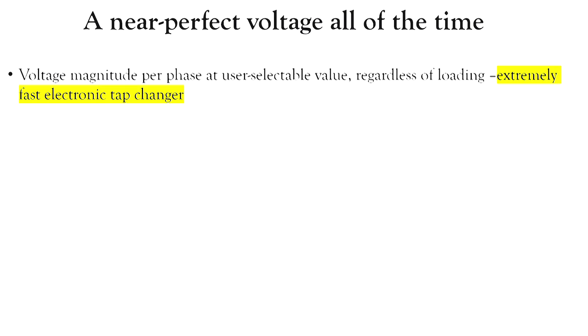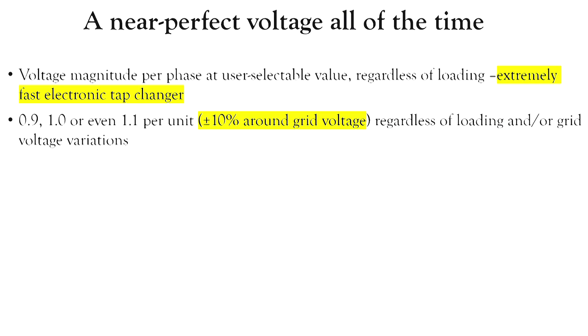Now, let's say the example that me and Tanya are at the moment looking at, the voltage sits at 10.5 kilovolt. The client expects at least 11, but imagine that is the in-feed to a plant. There will be some voltage drops downstream. So his equipment is already below an ideal voltage. The motors suck in more current because voltage is less. They run hotter, they don't last. And many other problems can arise.